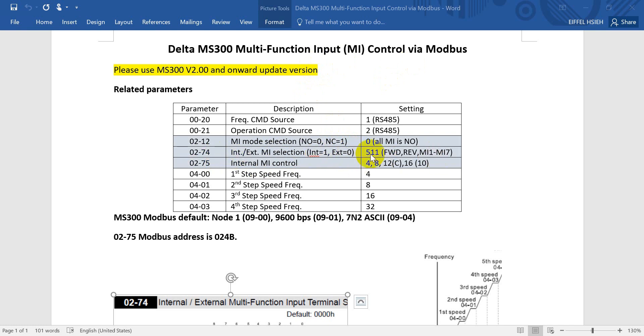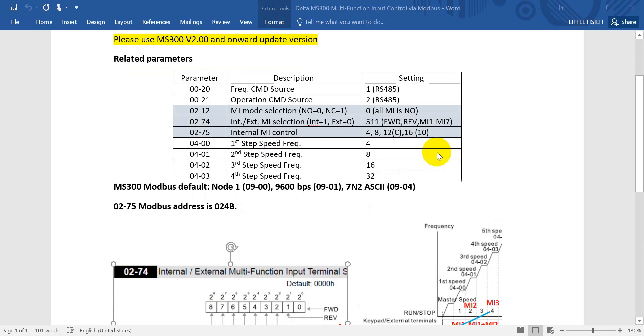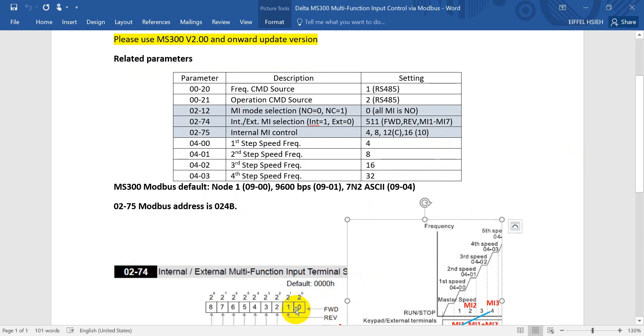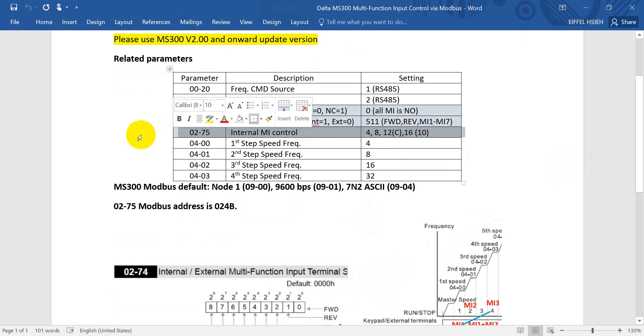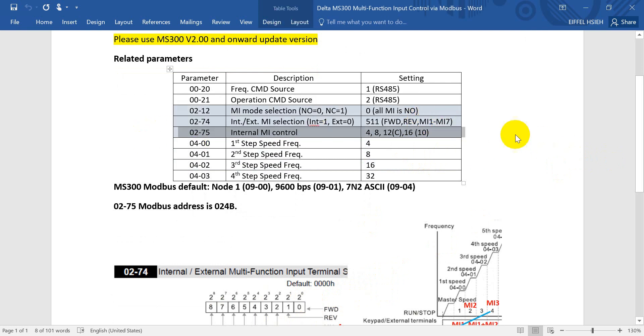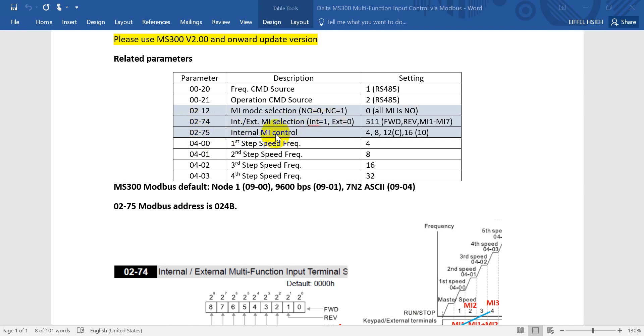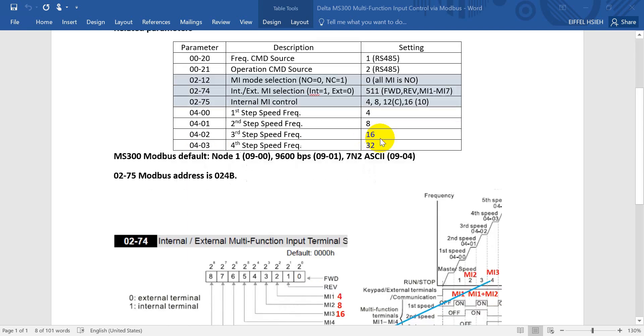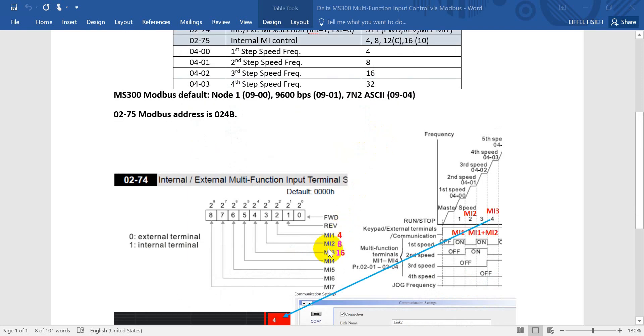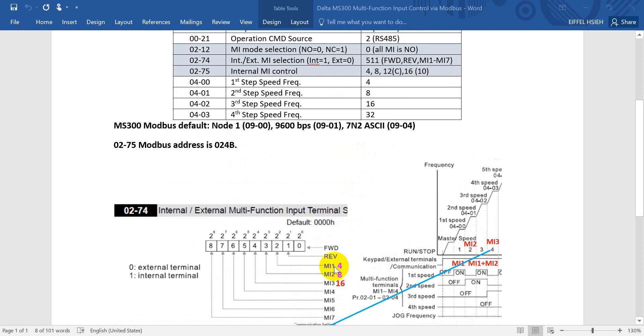Internal means we can use Modbus to control, but if you define it as external, that means use the physical wiring. So in today's example I will define it as 511. 511 can refer to the definition over here. Today I'll basically just show you MI1 to MI7. Next is P02-75. This one is internal MI control.